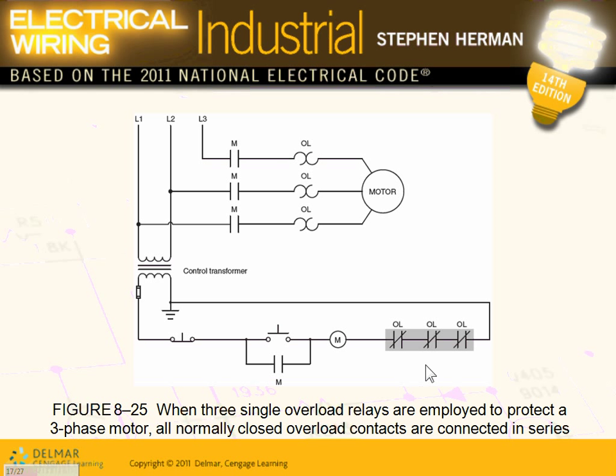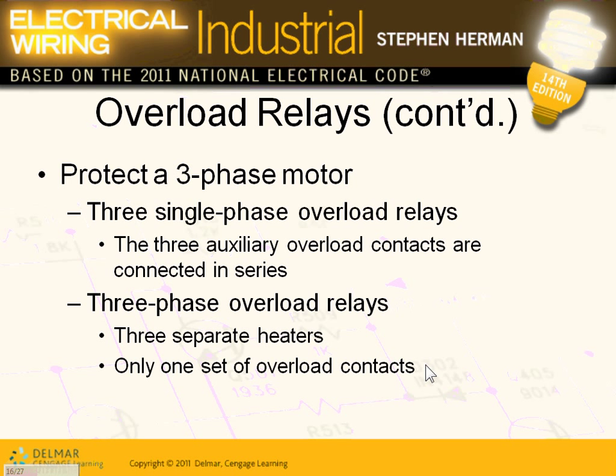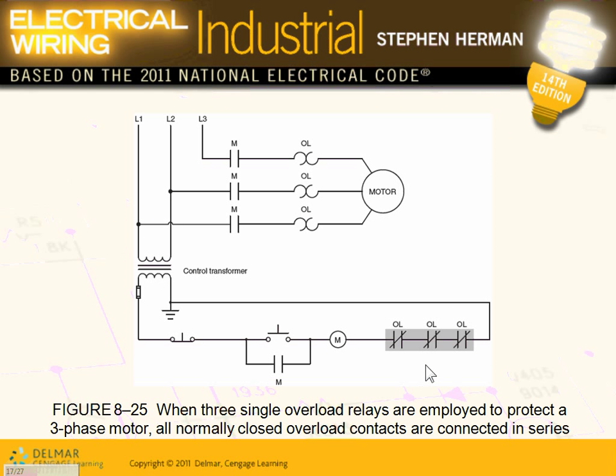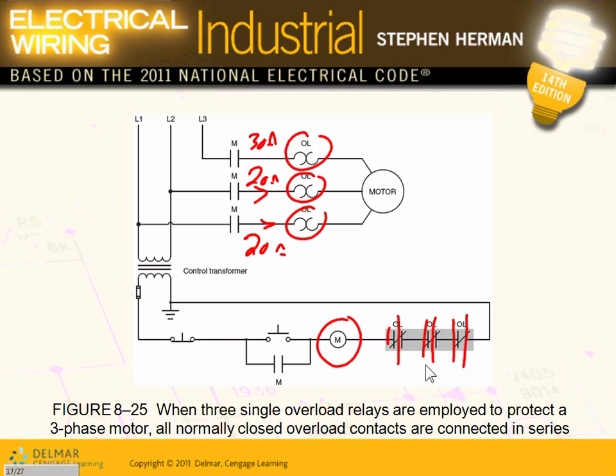Three-phase overload relay heaters: in this case you have three single overloads — one, two, three — each one in a phase. Each one can open the circuit. So if phase A is 20 amps, phase B is 20 amps, but phase C is 30 amps, something is wrong in phase C. That overload relay will open. Any one of the three can de-energize the circuit — if you open any one of them, the coil will be de-energized and the contacts will open.